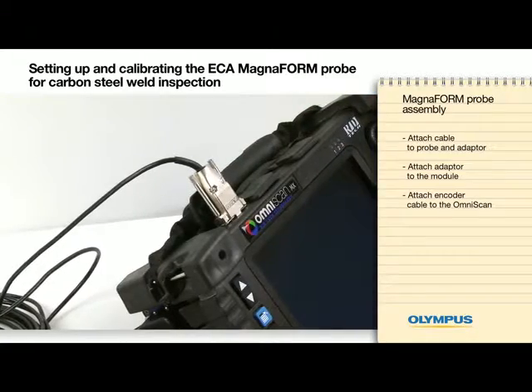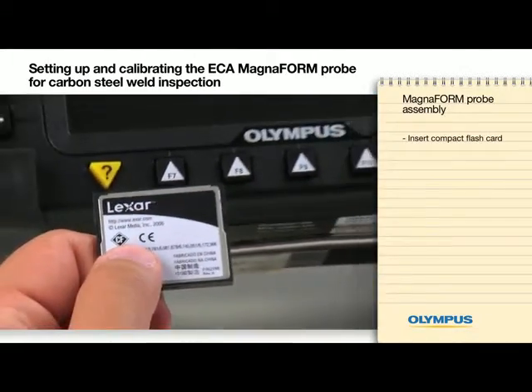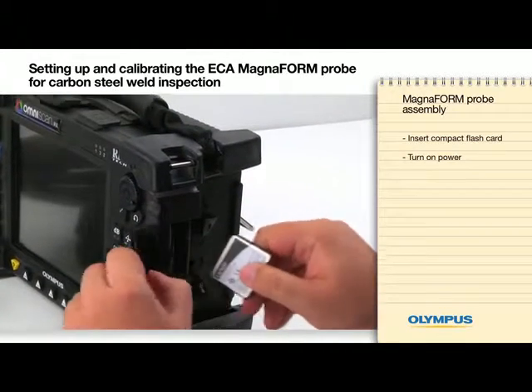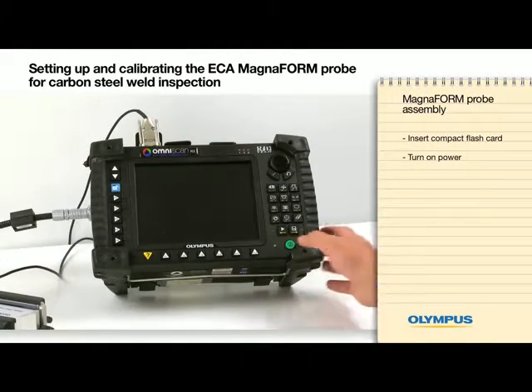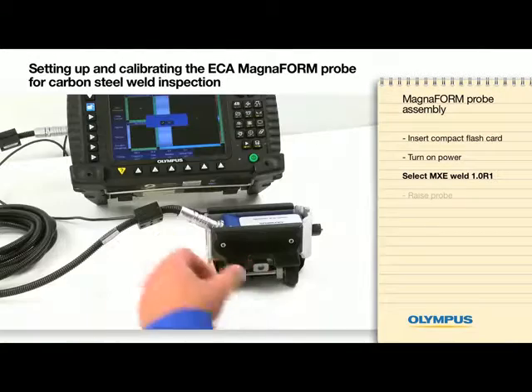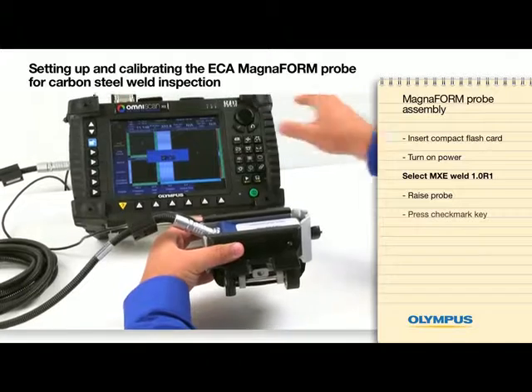You are now ready to start the application. Insert the compact flash card into the OmniScan MX and power on the instrument. Select MXE Weld 1.0R1, then raise the probe and press the checkmark key.